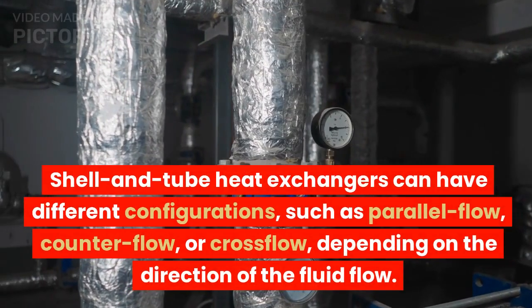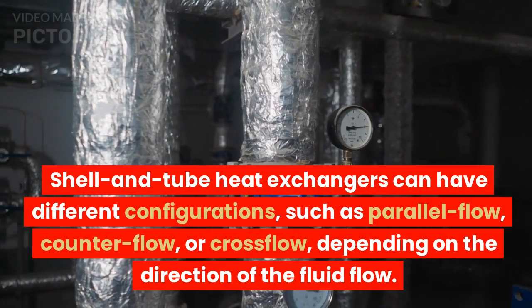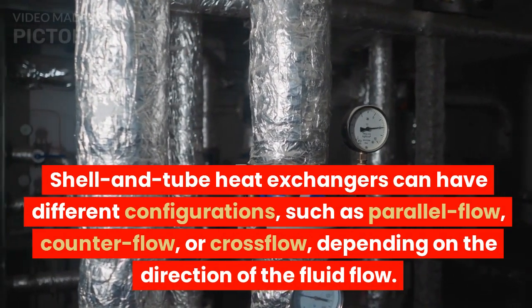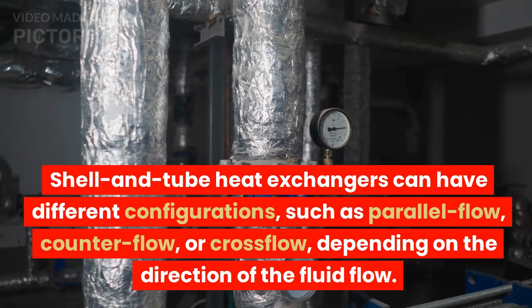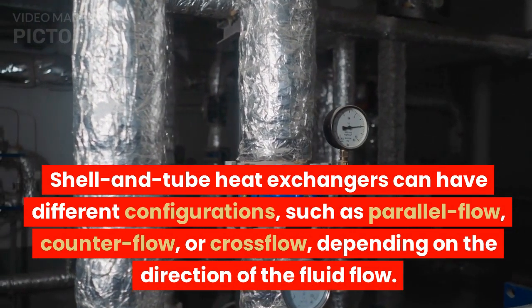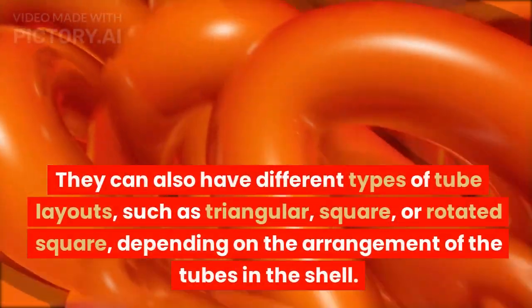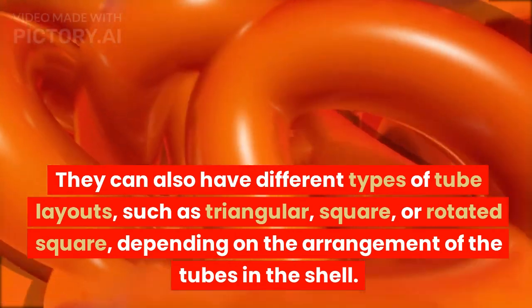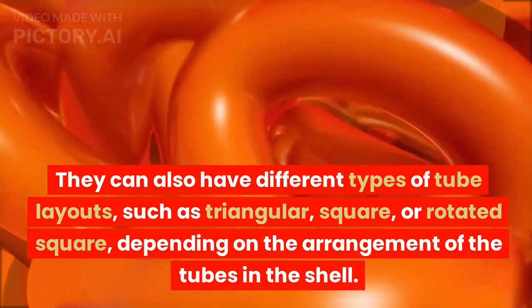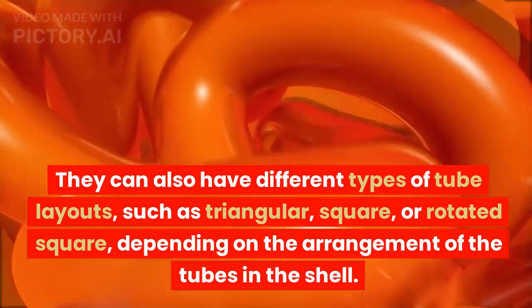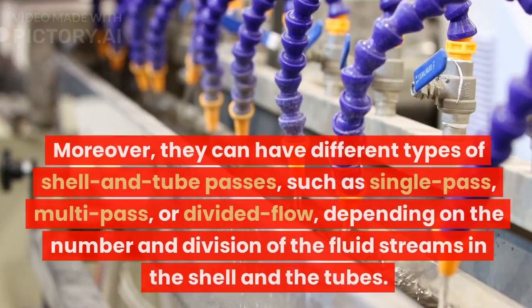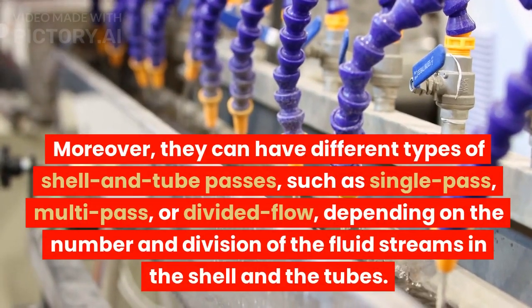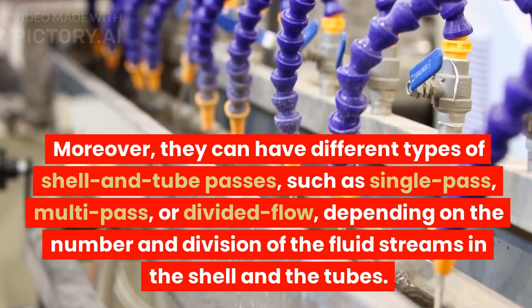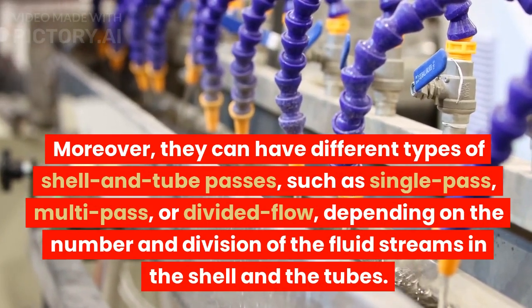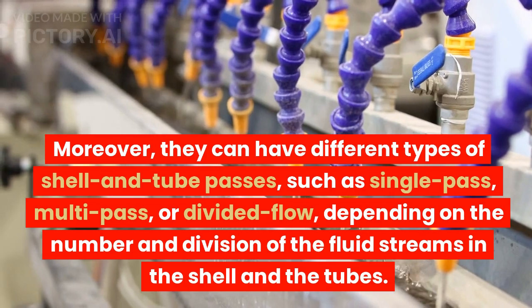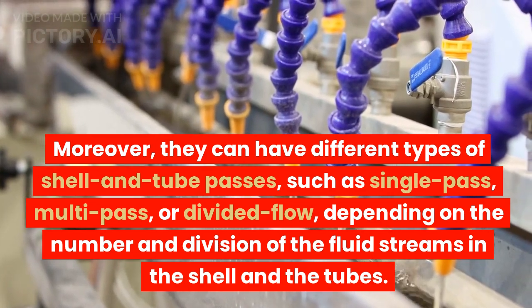Shell and tube heat exchangers can have different configurations, such as parallel flow, counterflow, or cross-flow, depending on the direction of the fluid flow. They can also have different types of tube layouts, such as triangular, square, or rotated square, depending on the arrangement of the tubes in the shell. Moreover, they can have different types of shell and tube passes, such as single pass, multi-pass, or divided flow, depending on the number and division of the fluid streams in the shell and the tubes.